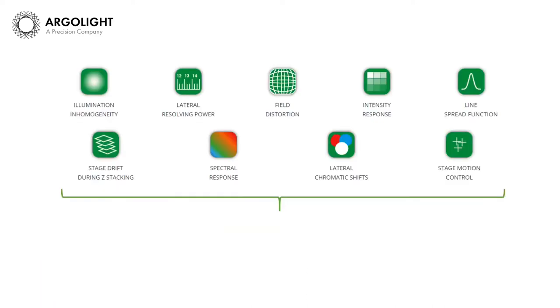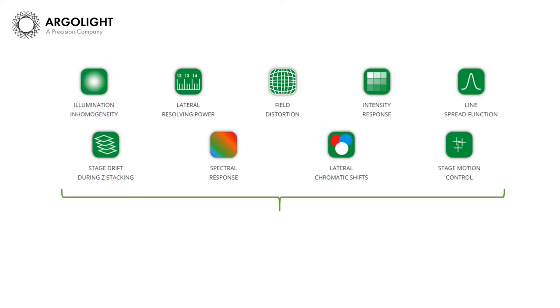With Daybook Analysis, you will be able to measure the performance of your system on up to nine different analysis domains. You will be able to measure illumination inhomogeneity, lateral resolving power, field distortion, intensity response, line spread function, stage drift during Z-stacking, spectral response, lateral chromatic shift, and stage motion control.